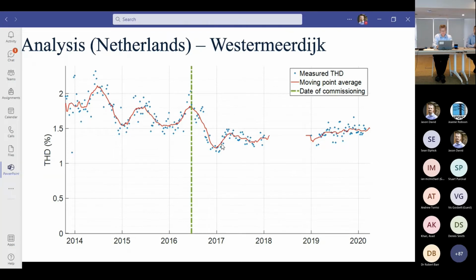Looking at another site, Westermeerdijk, again we see these seasonal variations, but ultimately the trend is on a downward slope through until the date of commissioning, at which it again flattens out. We've got about a year's worth of data missing, but we pick it up once the data is available again, and see a much smoother level of distortion occurring at that substation itself. So what does all of this mean?